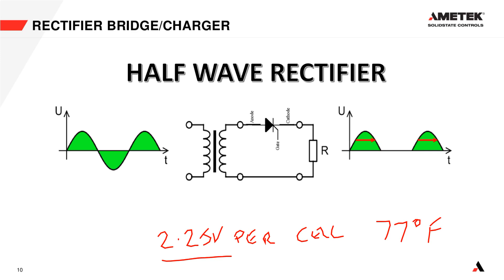There's one important thing to know about batteries: they need to be charged at a specific voltage. For lead acid batteries, it's usually 2.25 volts per cell at 77 degrees Fahrenheit. Some manufacturers specify different voltages, but roughly 2.25 to 2.27 volts per cell at 77 degrees Fahrenheit is standard. If you go outside that voltage, you'll either undercharge or overcharge the batteries.